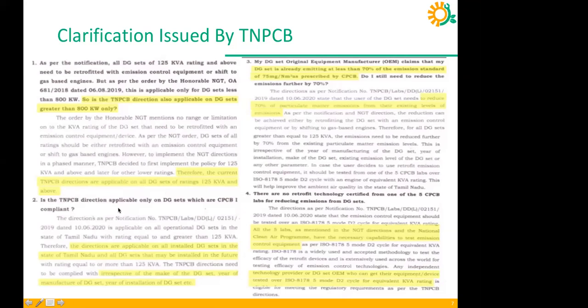People also asked: I have a DG maintained as per CPCB defined norms of mg per normal meter cube as required by PM standards, do I still have to go forward with retrofit technology? TNPCB answered that the directions are applicable on all installed DG sets in Tamil Nadu and all DG sets installed in future with rating equal to or more than 125 kVA. These directions must be complied with irrespective of make, year of manufacture, or year of installation of the DG set.